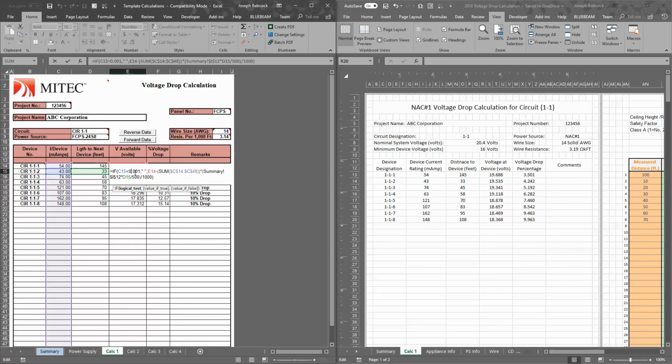And this may be just for a safety factor, but this column, or this summation formula, takes into account all of the current draw for every step down the circuit that we calculate. So this step-by-step calculation actually calculates everything in this column, where it should only calculate from the row that it's on and down.